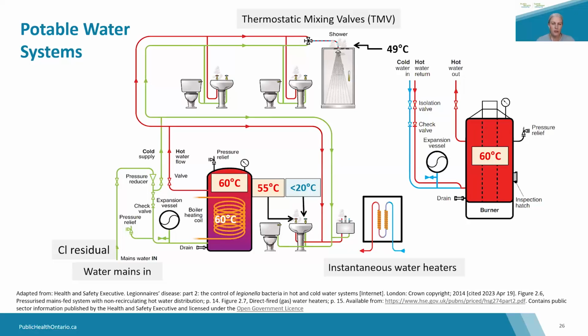Now, this can be a challenge for long-term care homes and healthcare settings to maintain those hot water temperatures without presenting the risk of scalding to residents and patients. So depending on the setting, there may be legal requirements for hot water temperatures to not exceed 49 degrees Celsius at the point of use. But in healthcare settings, thermal mixing valves can be considered to maintain water temperatures throughout the system while preventing scalding. And a thermal mixing device or thermal mixing valve is essentially a device that is used to blend hot and cold water together at the point of use.